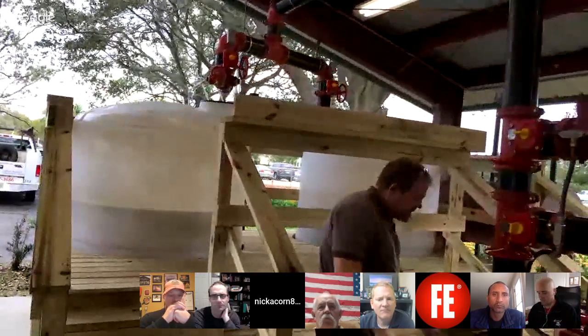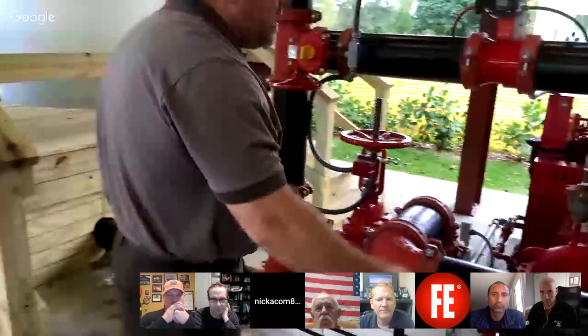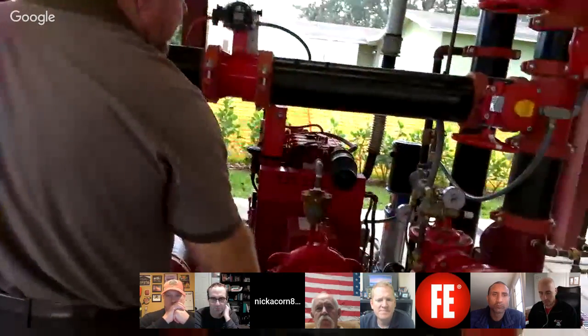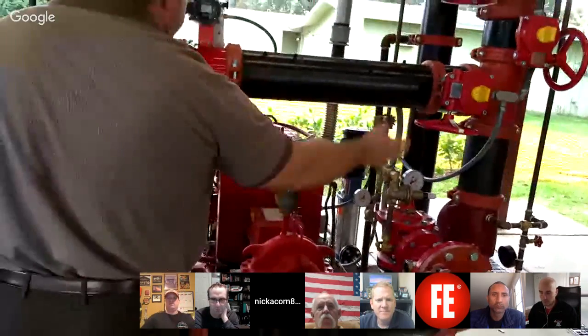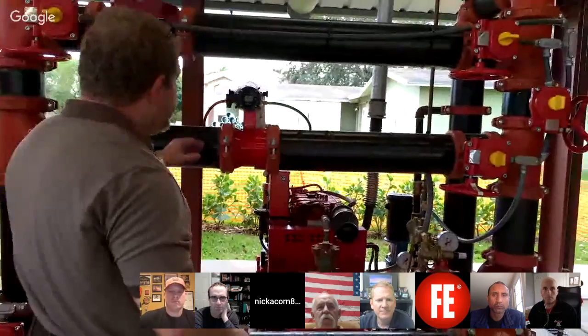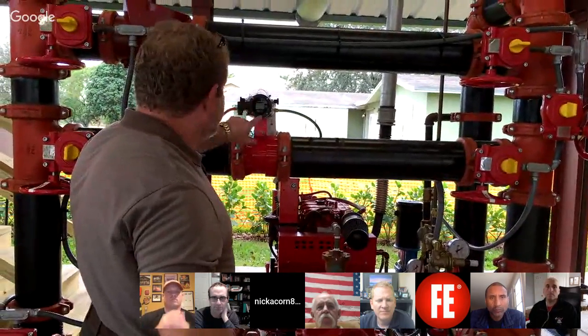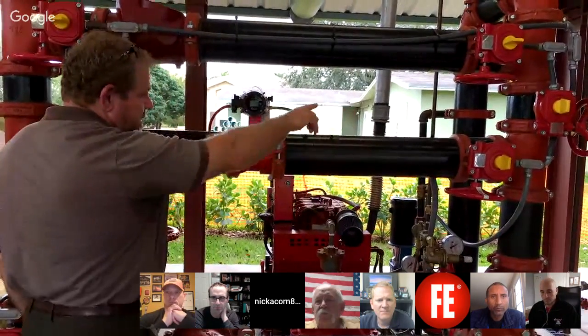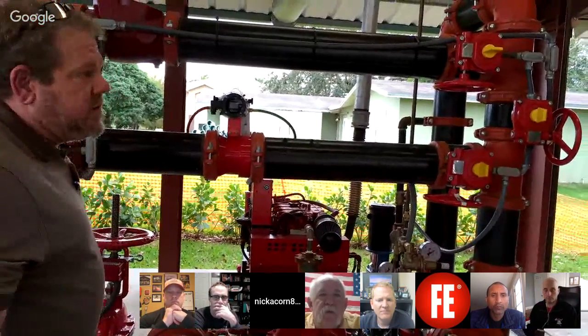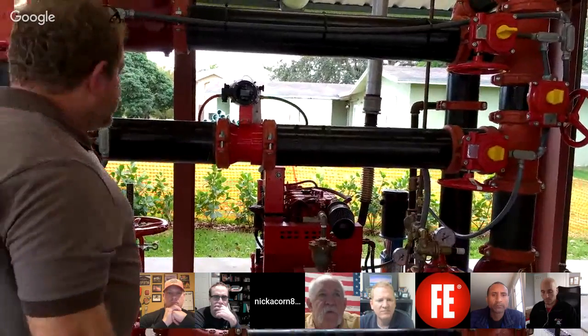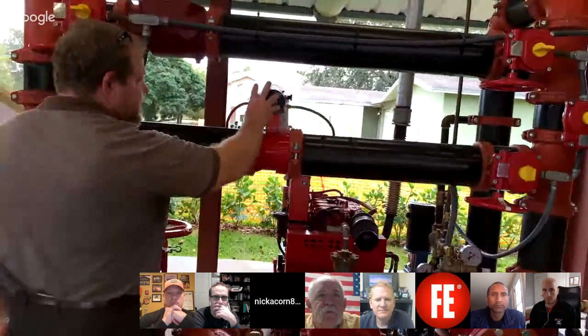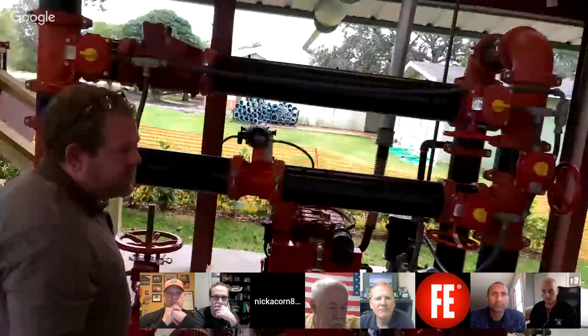Gravity fed, comes into the diesel fire pump. We've got two different applications to test the fire pump. Got a flow meter, so we're able to recirculate the water. We're waiting for programming, so this is a digital flow meter. It's reading in GPM and should graph onto the controller. We literally just got the program, and we're making the connection, so we should be able to actually see the pump curve on the controller. That's pretty neat. That's state of the art.